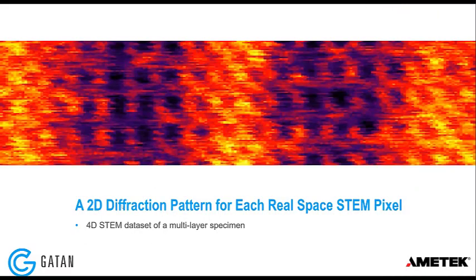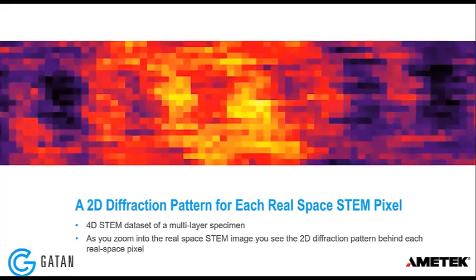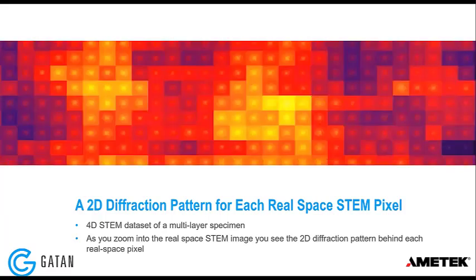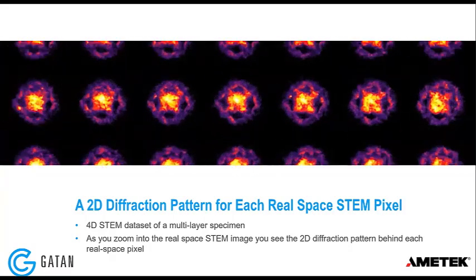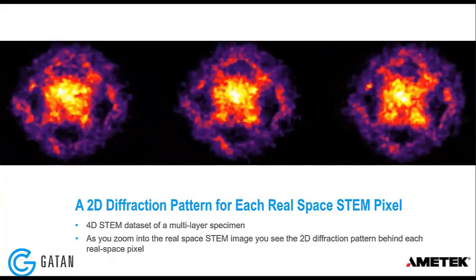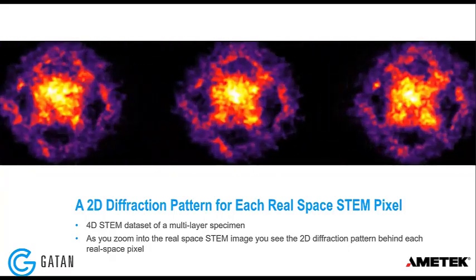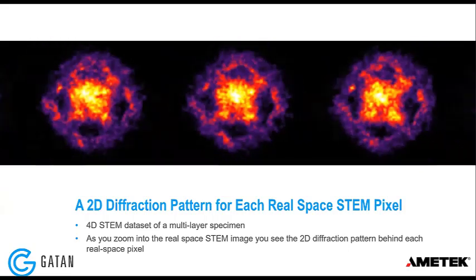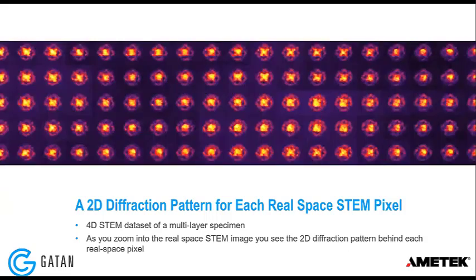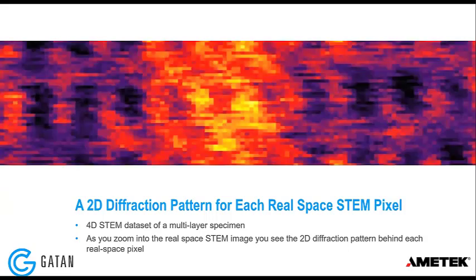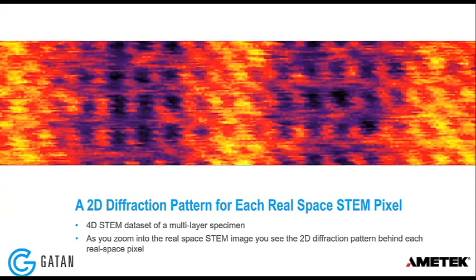We talked about what 4D STEM is. As you saw during the experiments that Roberto just showed us, at each probe position in a two-dimensional scan, we collect a two-dimensional diffraction pattern — that's why this is commonly called a 4D STEM experiment. So you have two-dimensional diffraction and two-dimensional scanning of the sample.